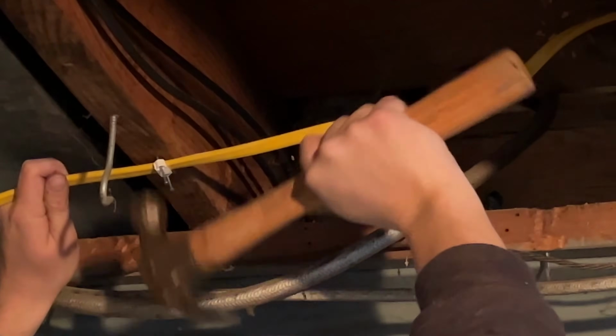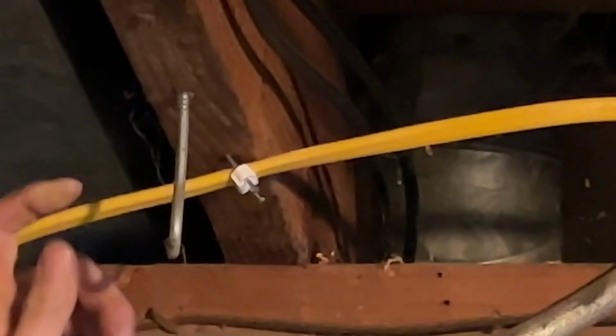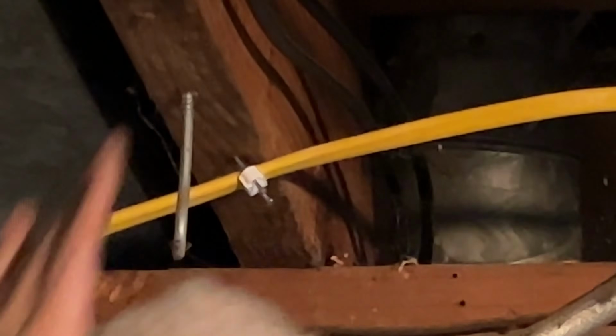Here in the basement, we're going to drill through the joist and run the Romex wire right in the center of the floor joist. That is best practice. As there were some heating ducts in our way and we're very close to the electrical panel, it was easy just to go under the joist. Do remember to do your wire staples every few feet and within a few inches of the electrical panel.